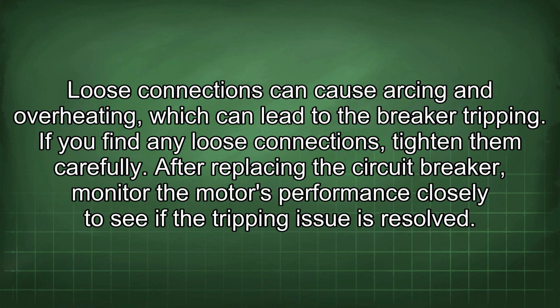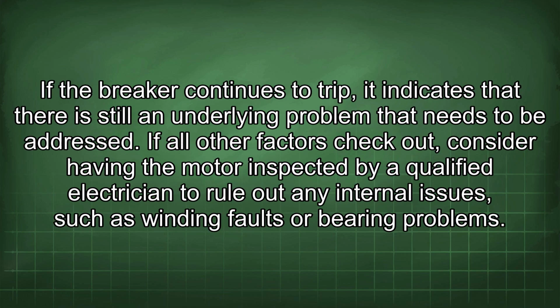Loose connections can cause arcing and overheating, which can lead to the breaker tripping. If you find any loose connections, tighten them carefully. After replacing the circuit breaker, monitor the motor's performance closely to see if the tripping issue is resolved. If the breaker continues to trip, it indicates that there is still an underlying problem that needs to be addressed.